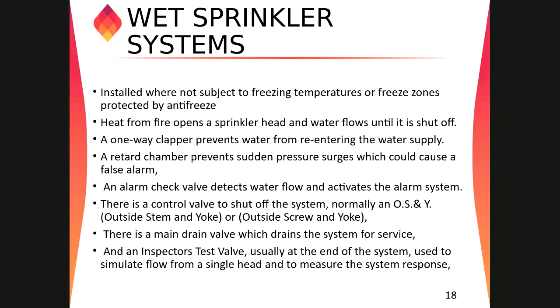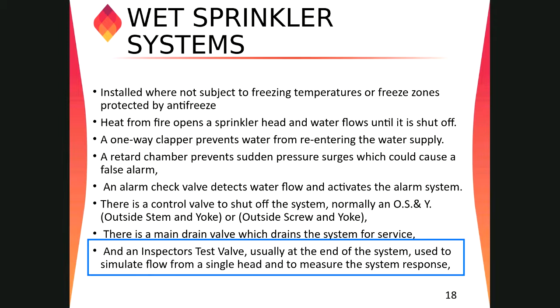The one I was discussing is the inspection test valve. Here we have the inspection test valve at the end of the system to simulate flow from a single head, a single sprinkler, and to measure the system response. System response means, when I start flowing water, after how much time there is an alarm, or after how much time the water flow switch activates.